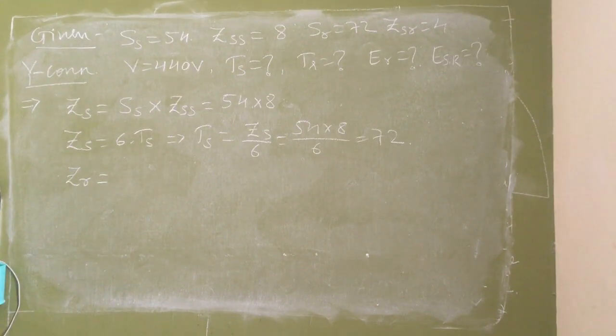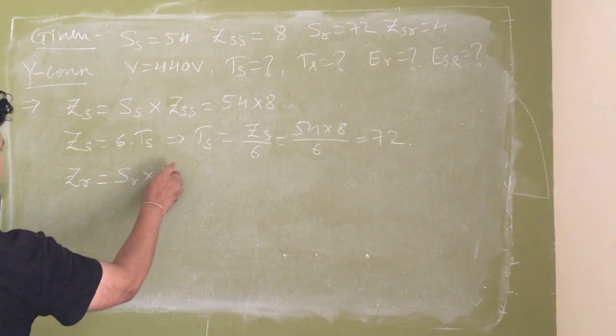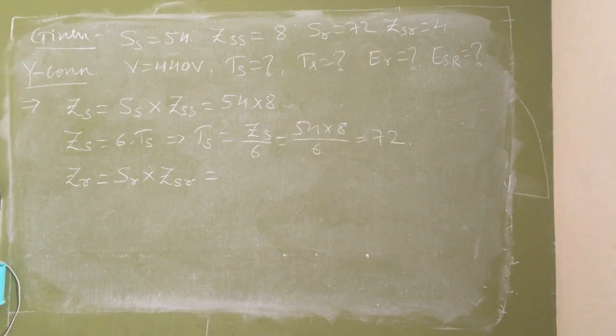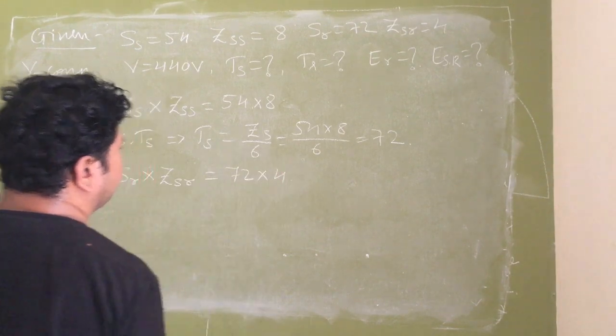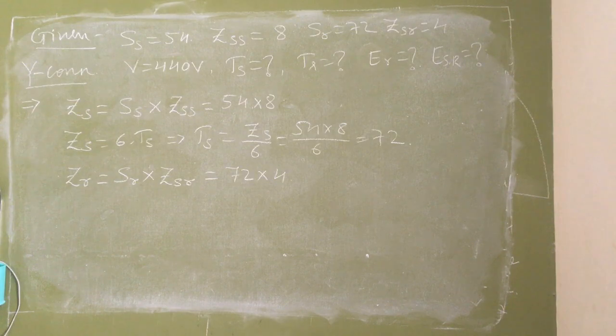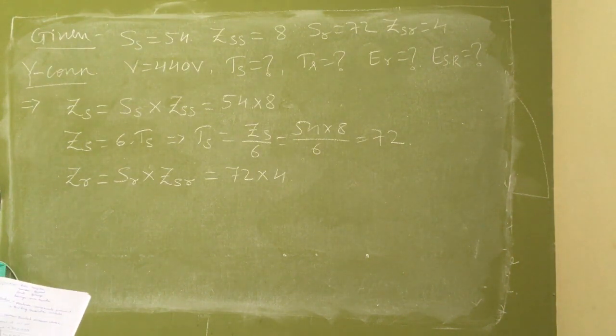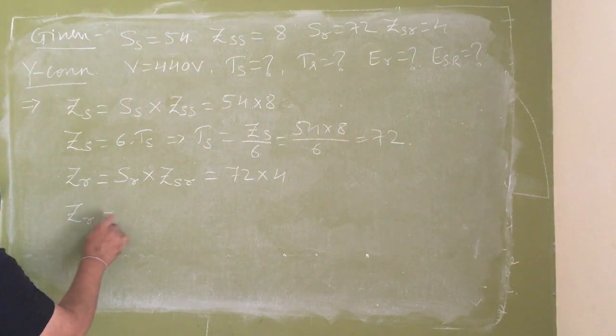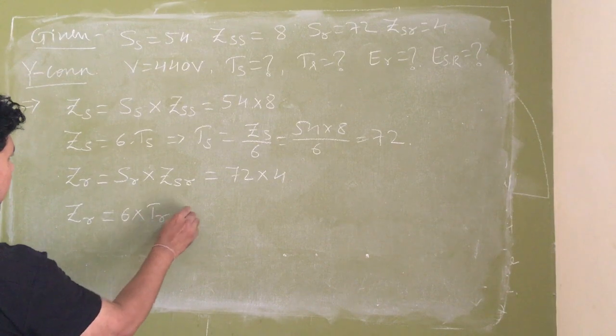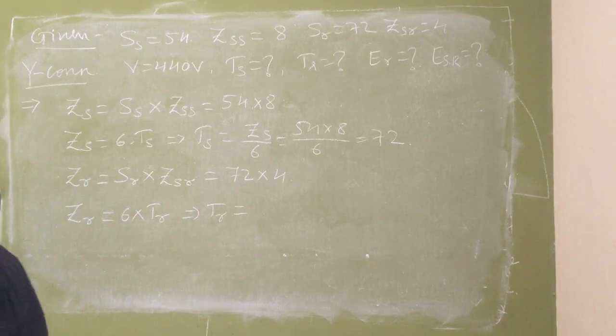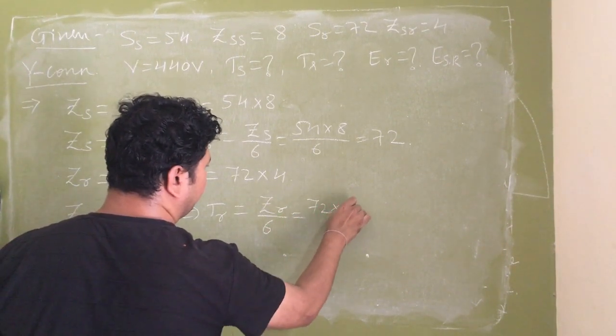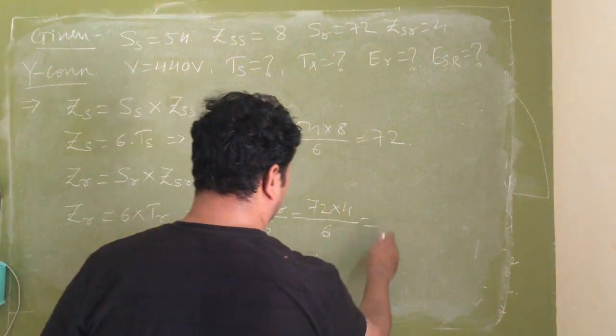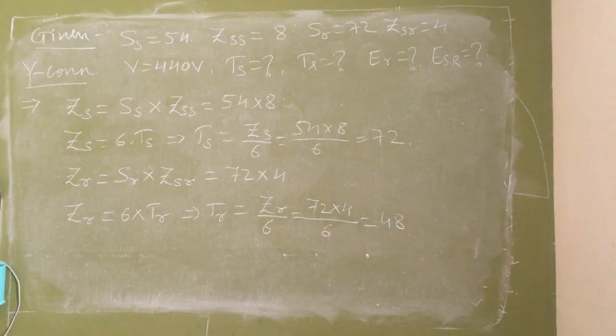Rotor conductors ZR = rotor slots × rotor conductors per slot = SR × ZSR = 72 × 4. Similarly, ZR = 6 × TR, so TR = ZR / 6 = (72 × 4) / 6 = 48. So the number of rotor turns per phase is 48.